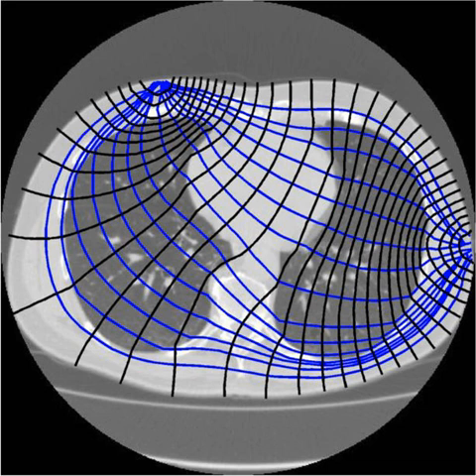EIT is particularly useful for monitoring lung function because lung tissue resistivity is five times higher than most other soft tissues in the thorax. This results in high absolute contrast of the lungs. In addition, lung resistivity increases and decreases several fold between inspiration and expiration which explains why monitoring ventilation is currently the most promising clinical application of EIT since mechanical ventilation frequently results in ventilator-associated lung injury. The feasibility of EIT for lung imaging was first demonstrated at Rensselaer Polytechnic Institute in 1990 using the NOSER algorithm. Time difference EIT can resolve the changes in the distribution of lung volumes between dependent and non-dependent lung regions and assist in adjusting ventilator settings to provide lung protective ventilation to patients during critical illness or anesthesia.